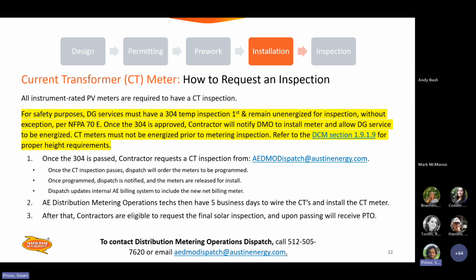So how to request an inspection. All instrument rated PV meters are required to have a CT inspection like I just addressed. For safety purposes, the DG service has got to have a 304 temp first, so everything's not energized, and this is without exception. Once the 304 is approved, the contractor will notify DMO to install a meter and allow the DG service to be energized. CT meters must not be energized prior to metering inspection.